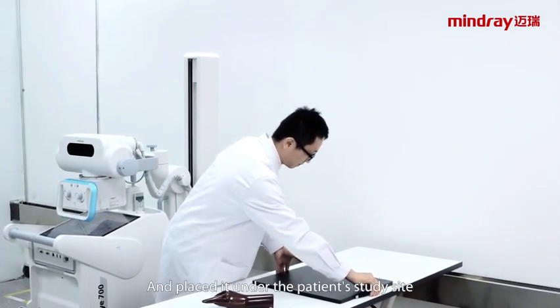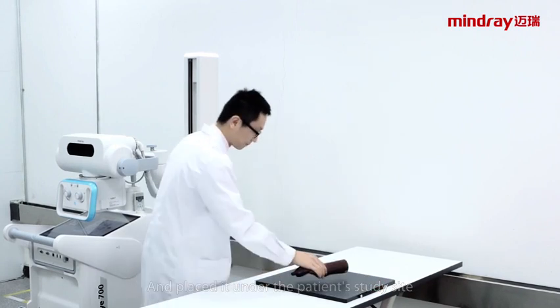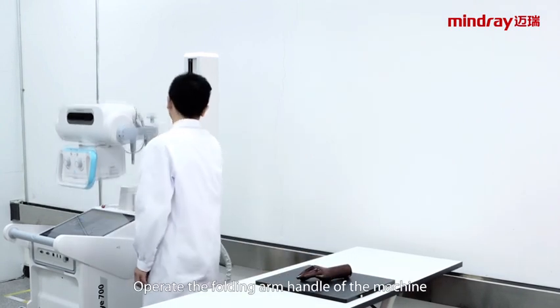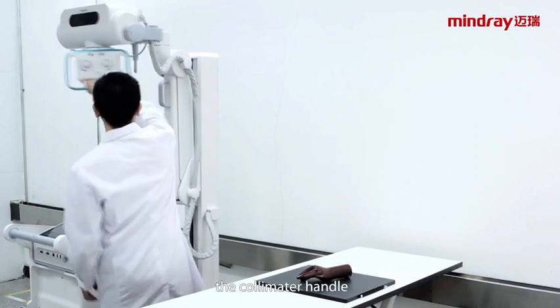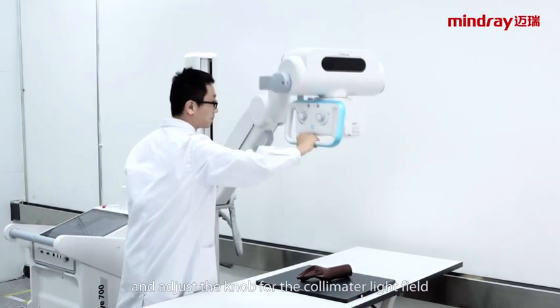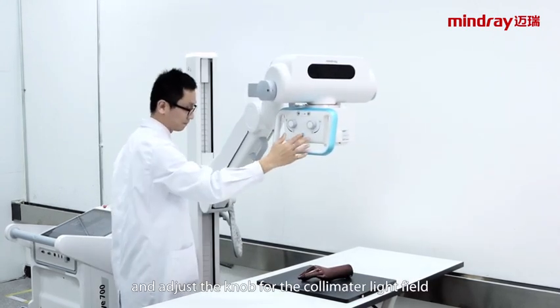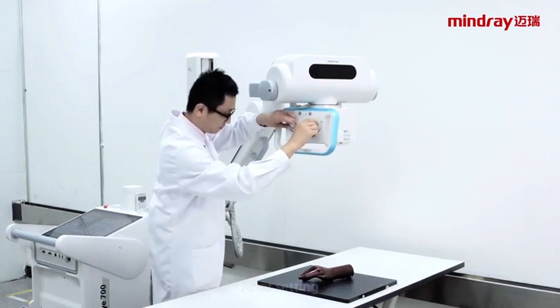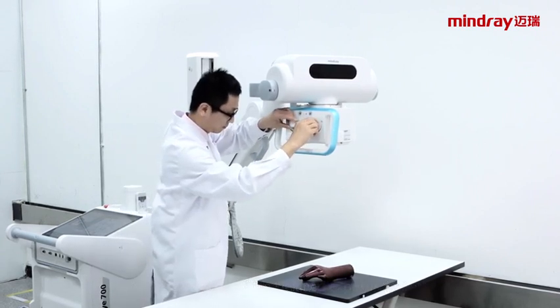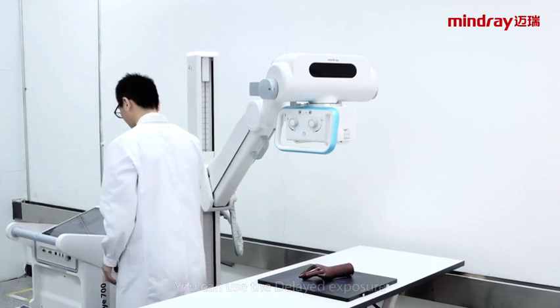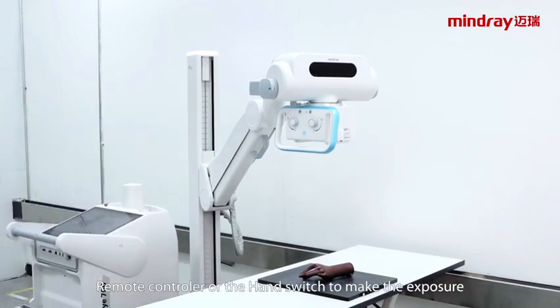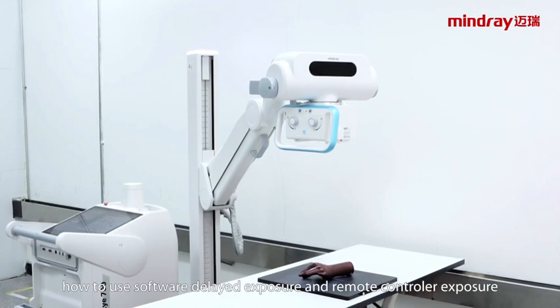And place it under the patient's study site. Operating the folding arm handle of the machine and the collimator handle, and adjust the knob for the collimator light field. After setting, you can use the delayed exposure, remote controller or hand switch to make the exposure. The following demonstrates how to use software delayed exposure and the remote controller exposure.